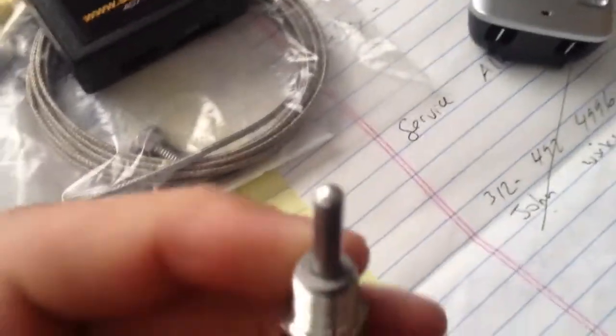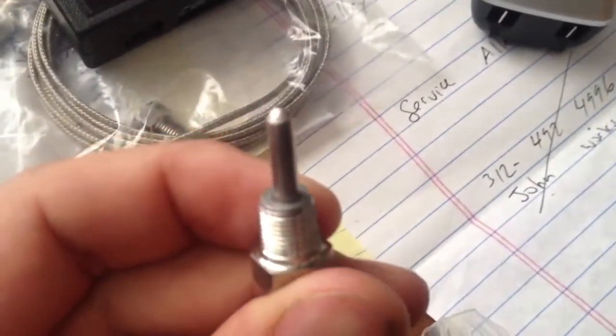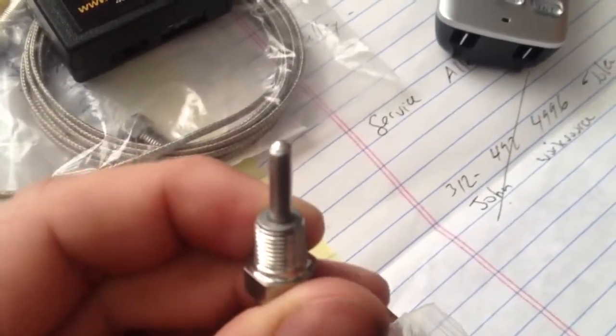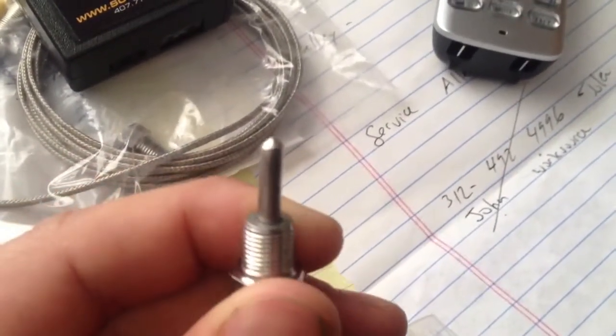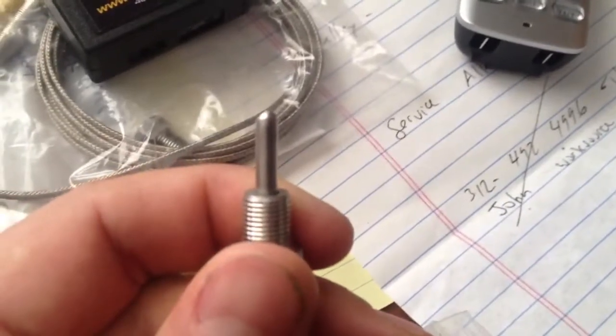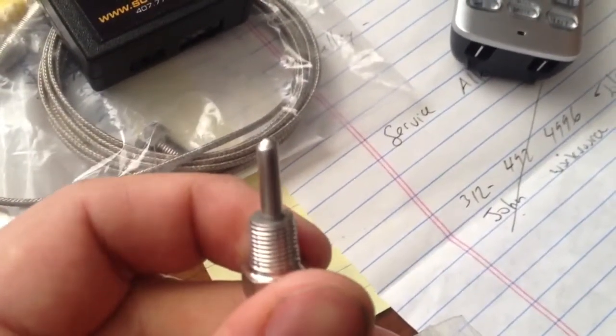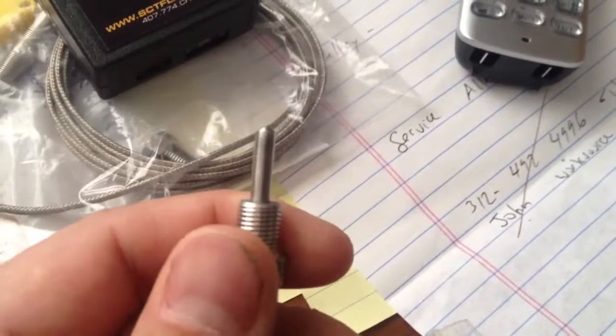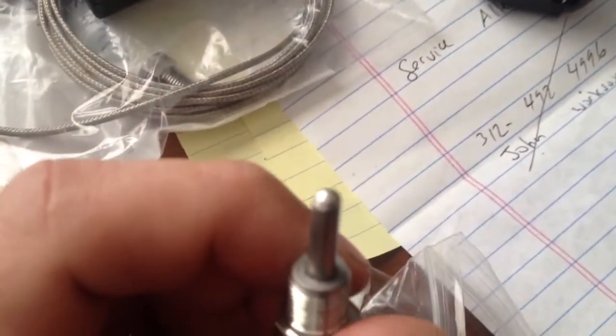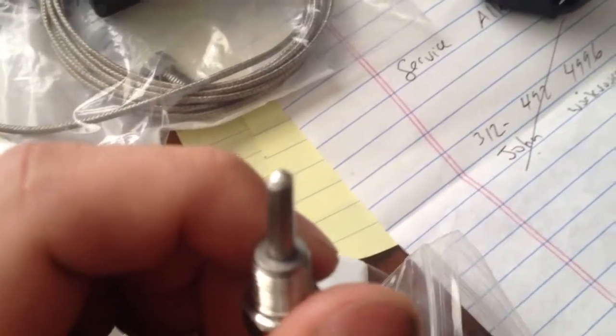But my question or concern with this one is, let me take it out and show you again, one second. When you're actually looking at the tip of this one, there's a crack in the very tip of the probe right there. You see that little black line? See if I can get it better in focus. Right there. You can kind of see too how it's got one flat side, like if you took a grinder to it, except it's really smooth. But anyways, that little black line there is an actual crack in the tip going more than half the circumference.